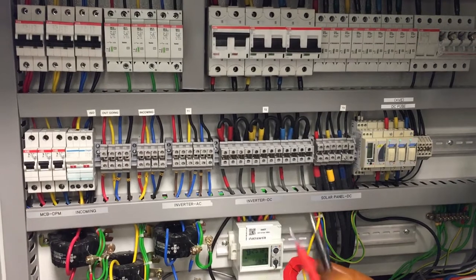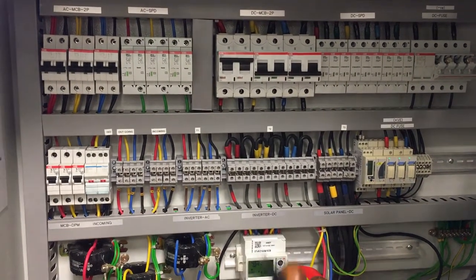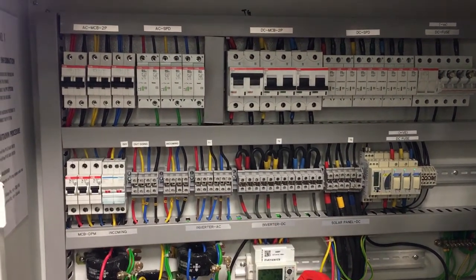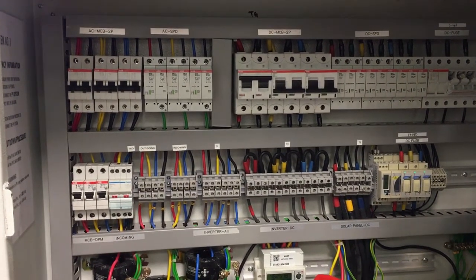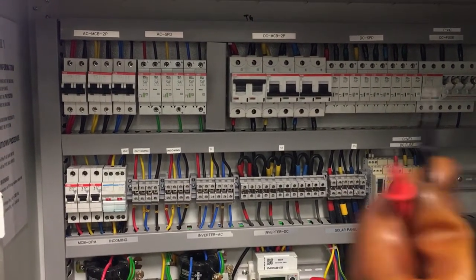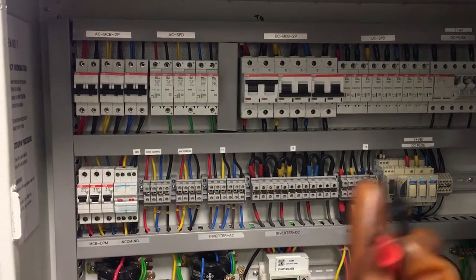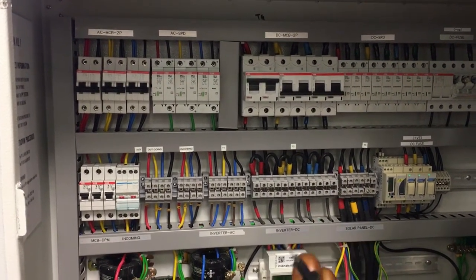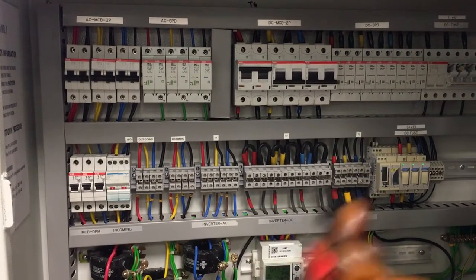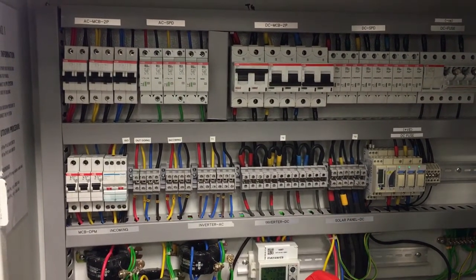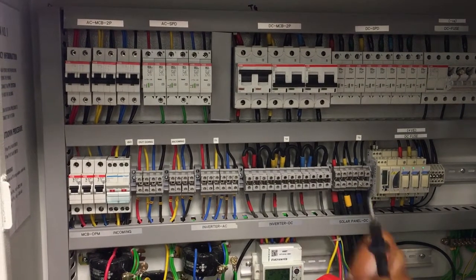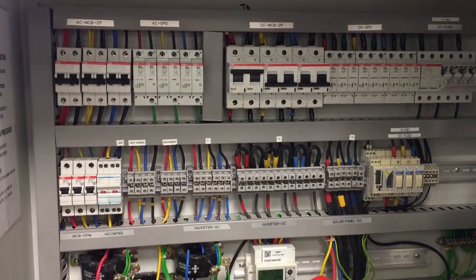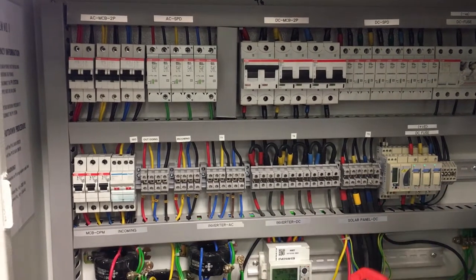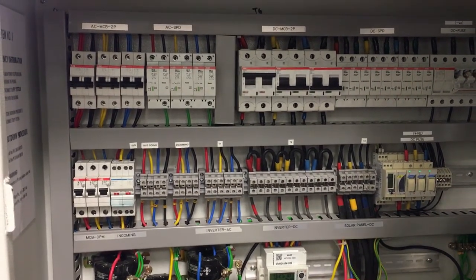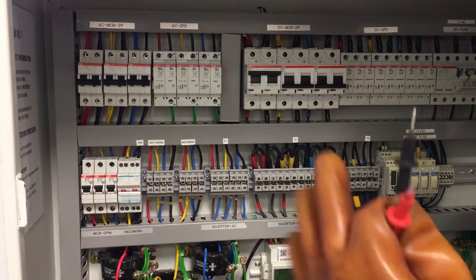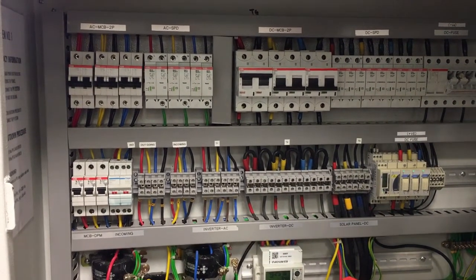Why is this? It's because when the grid supply is off, we do not want our PV system to supply power because it might be dangerous. Let's say TNB is doing maintenance at the line because of the fault. So if we supply power, then the technician will not know there is power coming from our PV system, and it can injure them, or in worst case scenario, it can even kill them. So that is why this concept is called anti-islanding. We do not want our PV systems to become their own islands and generate power to the grid without the knowledge of the grid operator.